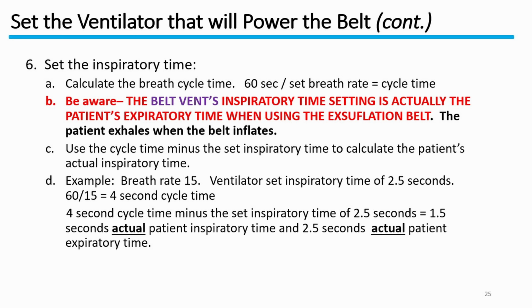For example, with a breath rate of 15, the ventilator set inspiratory time of 2.5 seconds. 60 divided by 15 gives a 4-second cycle time. A 4-second cycle time minus the set inspiratory time of 2.5 seconds gives 1.5 seconds actual patient inspiratory time and 2.5 seconds actual patient expiratory time. Let's look at another example.